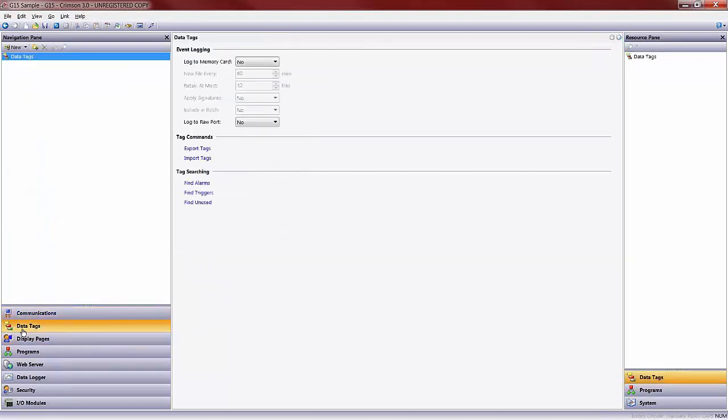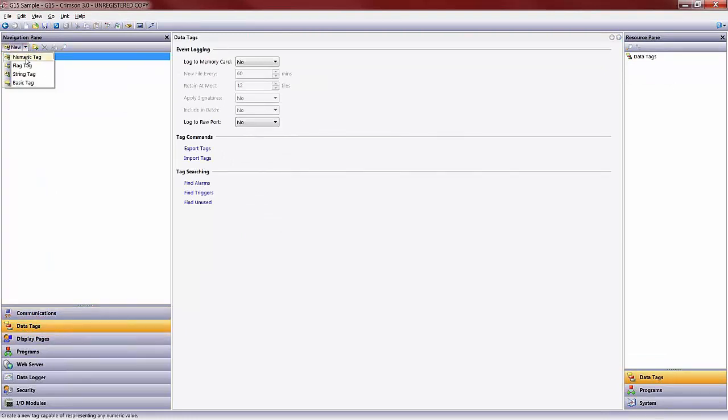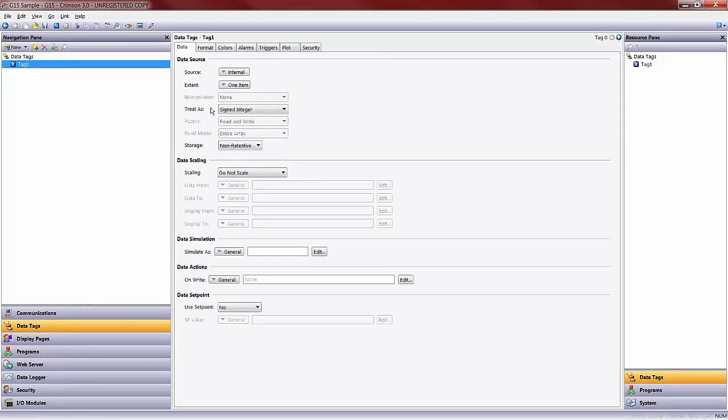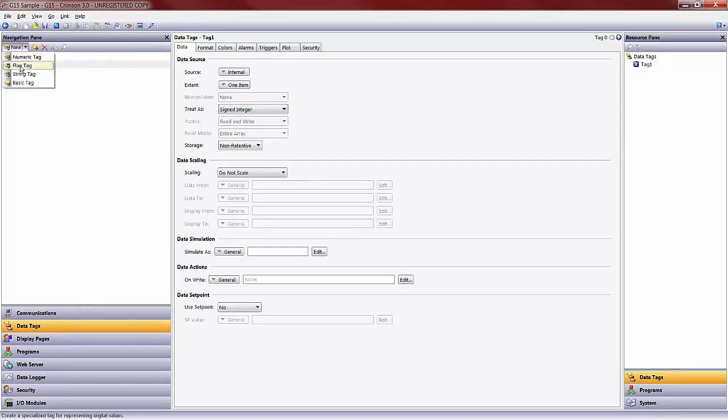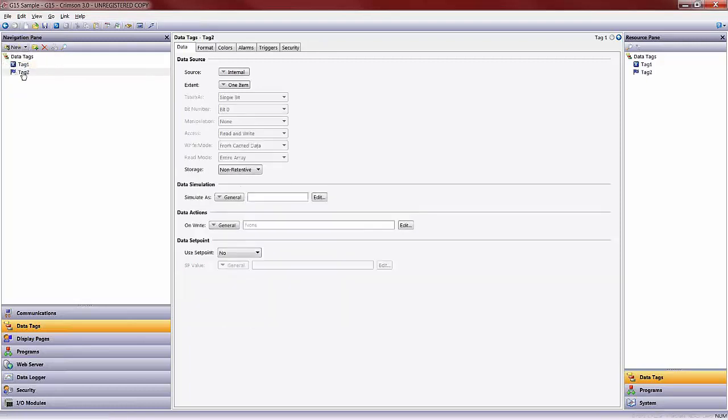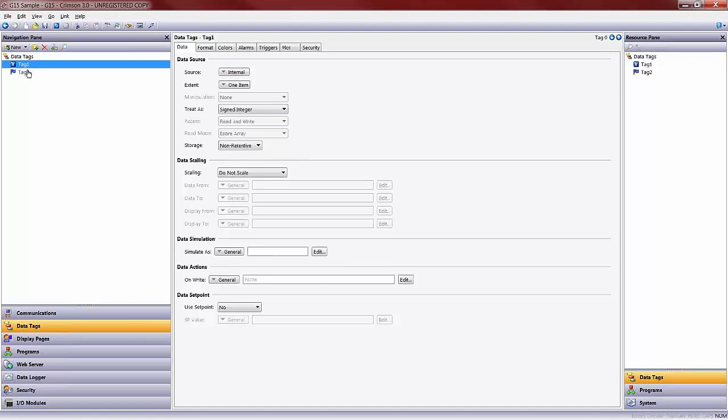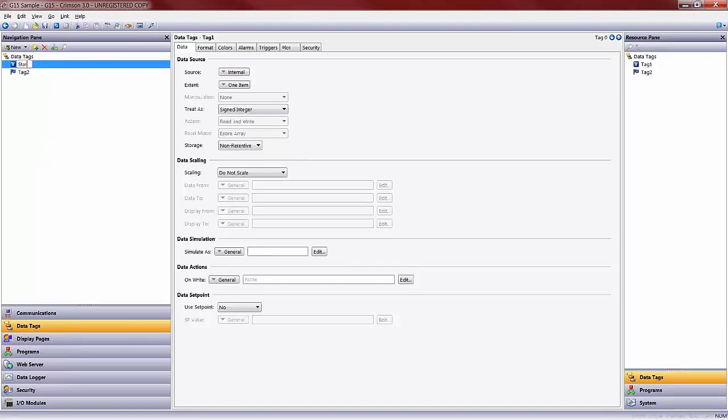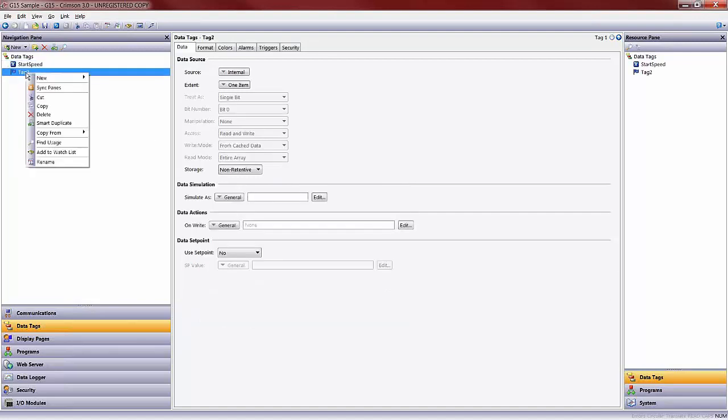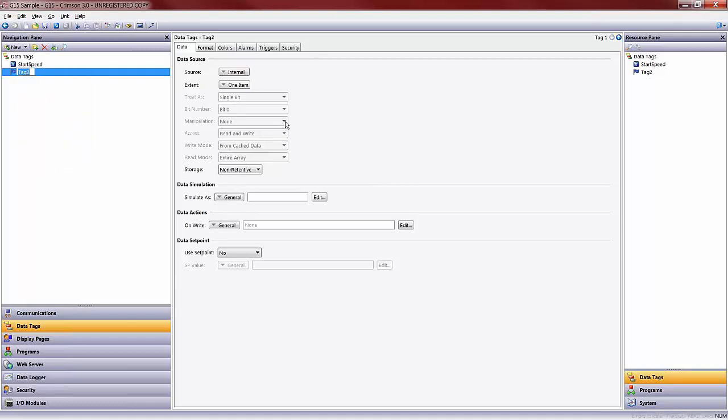We'll click on our data tags section in order to do so. I'll go up to my new and add a numeric tag, which can either be an integer or a floating point value. And I'll go ahead and add a flag tag as well. Flag tag is going to be a single bit or Boolean value, one or zero, on or off. I can rename these tags to be anything I want. For example, I could right click on tag one and rename this to be my start speed as a set point. And I could rename this flag tag to be my motor status.